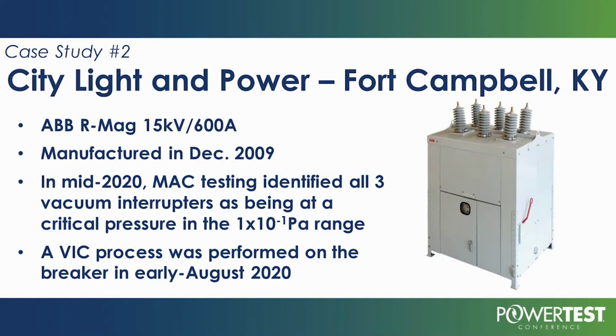Now let's move on to the next slide, which is our second case study. It's for a military base in Kentucky where we were called out because they had vacuum interrupters and outdoor breakers that were testing near failure, and they didn't want to have to replace them all. So we went out and did a conditioning process where we went out, conditioned the interrupters, went away for months, then came back, measured them again, and showed them the difference in pressure and the fact that the difference in pressure did live.